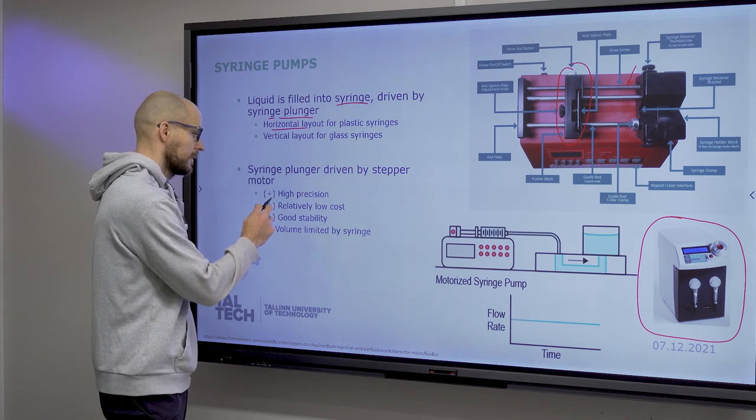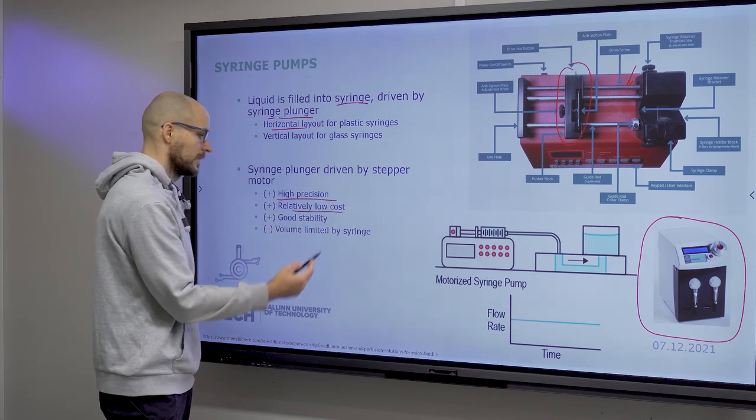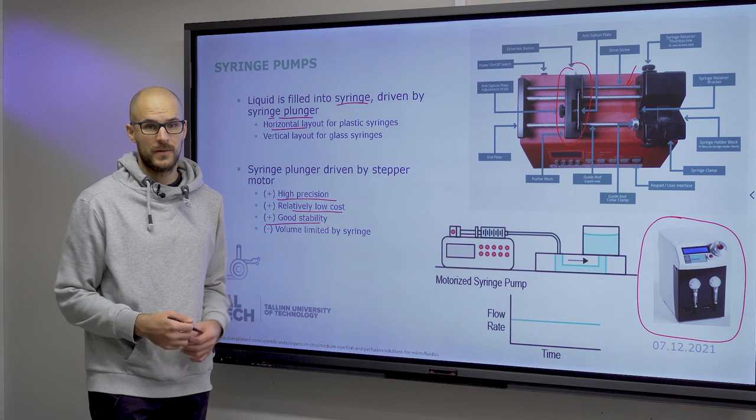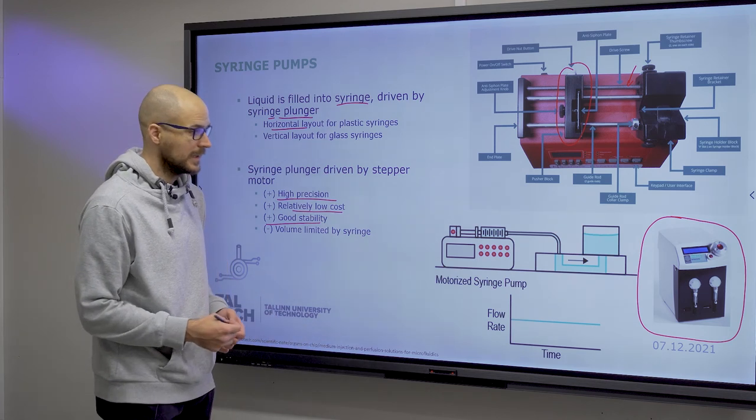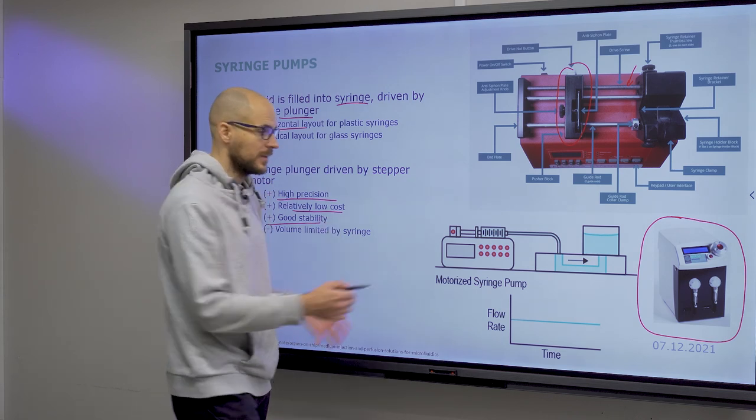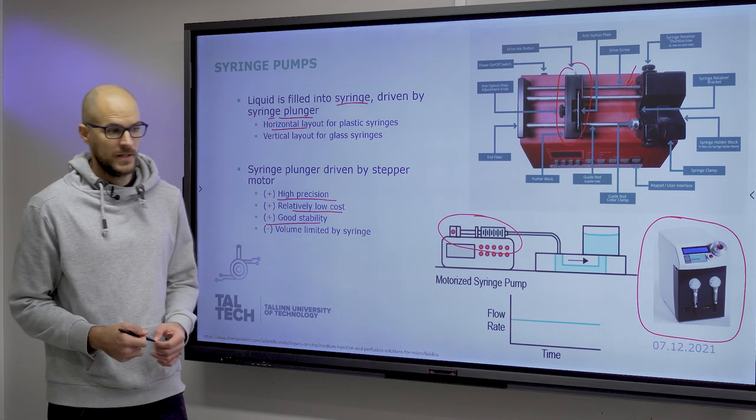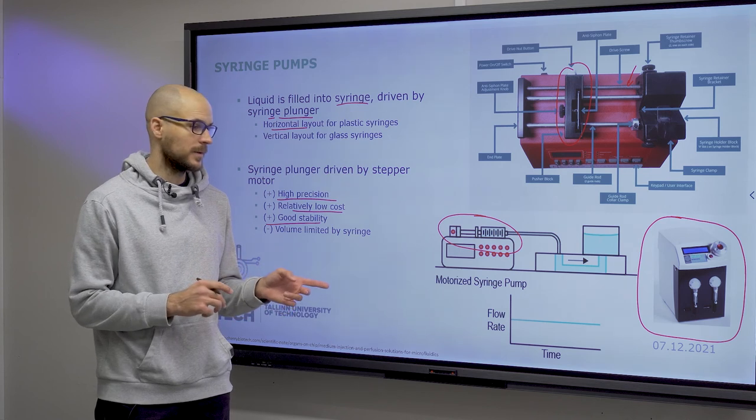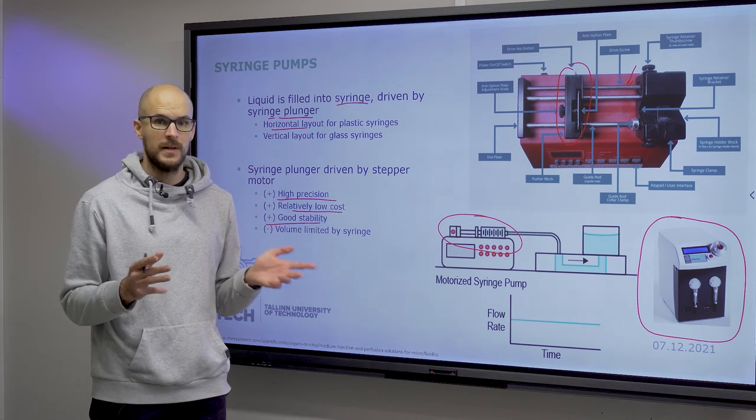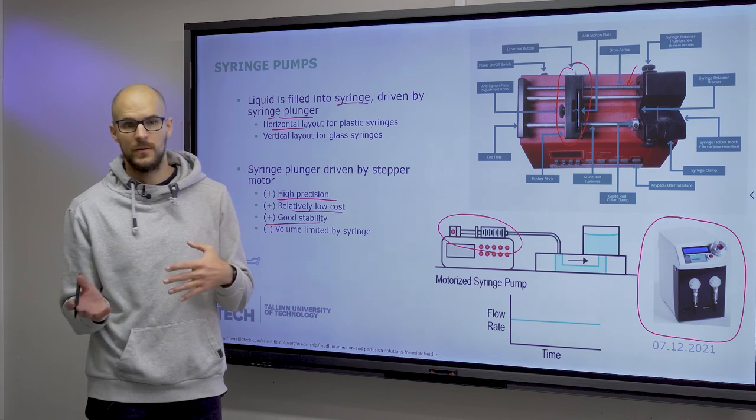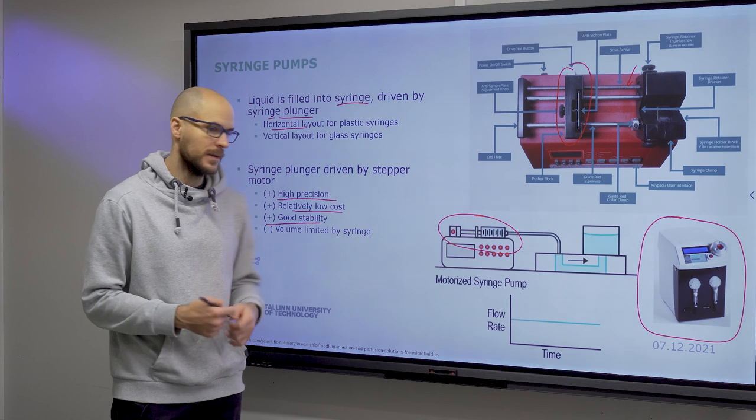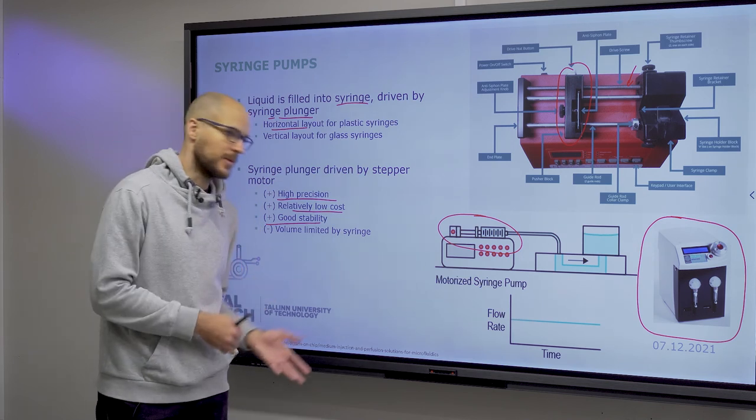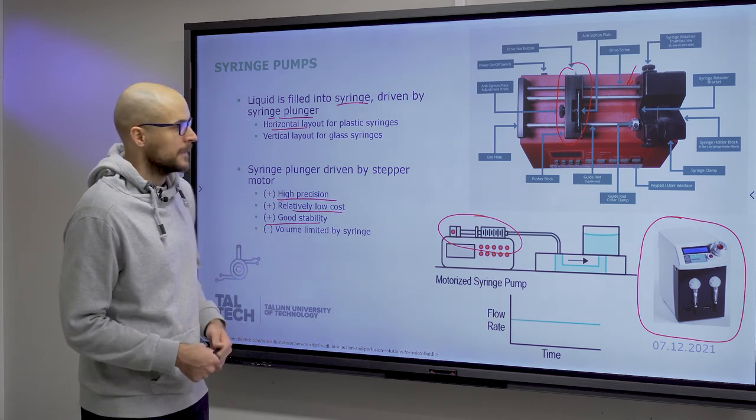Advantages, as I stated before: high precision, relatively low cost, good stability. However, the volume is limited by the size of your syringe. Even though you have all these advantages, having to reload the syringe is a problem. But you can have a three-state valve which can connect input and output, and then you can select whether you want to fill or empty your syringe. You can solve it in a way that you don't have to disconnect the syringe every time, but it is still uncomfortable that you need to fill up your syringe and then keep pumping.